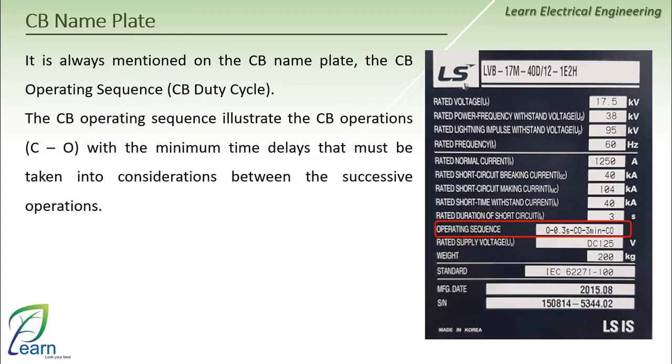Considering the timing that must be present between the operating cycles, my application now will be on the medium voltage circuit breaker with a spring type mechanism, which consists of two springs, one for closing and one for opening. A video will now appear in front of you, showing how the operating cycles are performed on the circuit breaker spring type mechanism.